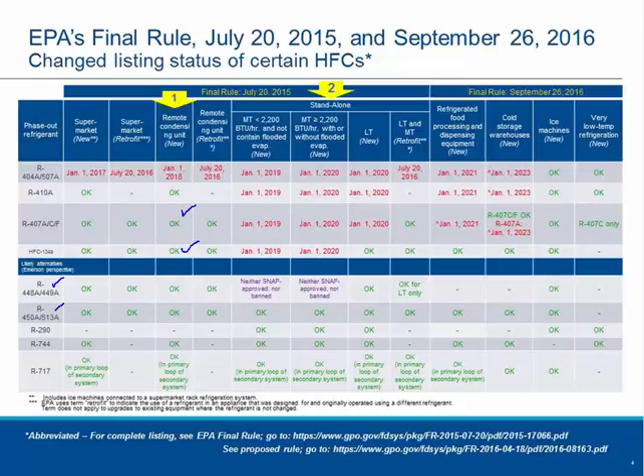On the self-contained side, on the factory charge systems, with 2019-2020 looming, the challenge that we are facing today as an industry is that there is currently no A1 alternative that has been SNAP approved. SNAP stands for the Significant New Alternatives Policy. It is an arm of the EPA that decides what refrigerants get delisted and what refrigerants get approved for some of these applications. So for now, there appears to be no alternative in an A1 category, non-flammable, for a 404A-like refrigerant. But as I mentioned to you a little earlier, 450 and 513A are 134A-like refrigerants. They are approved for medium-temp refrigerators and could be a good choice for medium-temp applications.